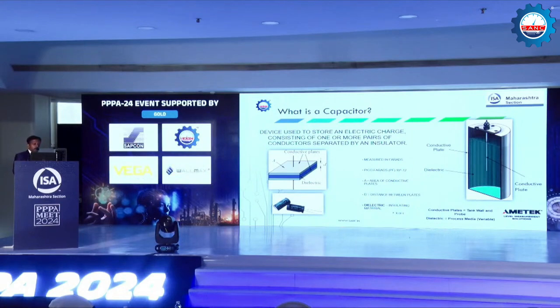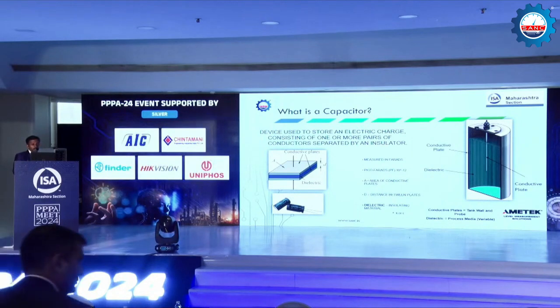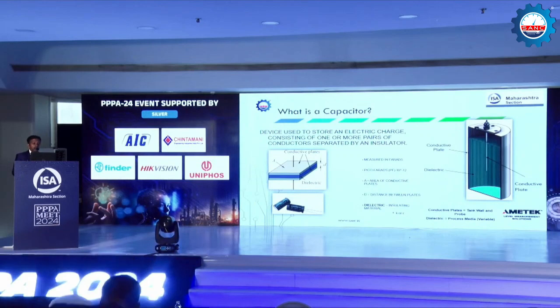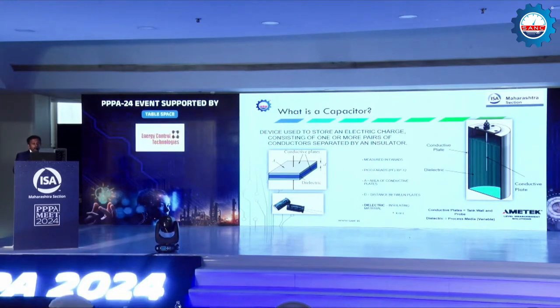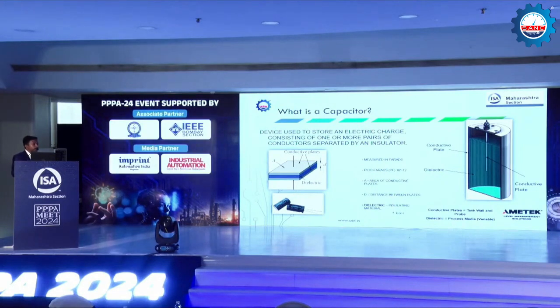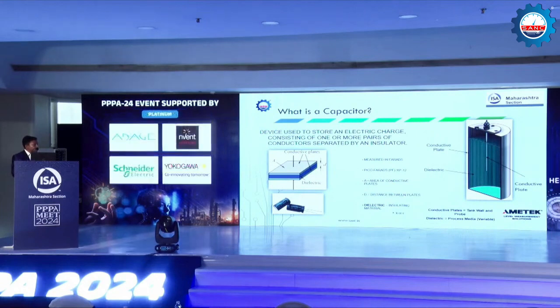What happens in the real world, in level applications, when you use the same technology? We are creating a big capacitor with a vessel where you are installing a transmitter or a switch. The right side picture is a cross-section view of an installation of a level transmitter. To create a capacitor, what do we need? We need two conductive plates. One conductive plate is the tank wall, which should be a conductive wall, a metallic wall. The other is the center rod from the transmitter. In between, the dielectric medium should be there. That is the actual measuring medium. Be it water, oil, or any kind of liquid, that is the dielectric medium.